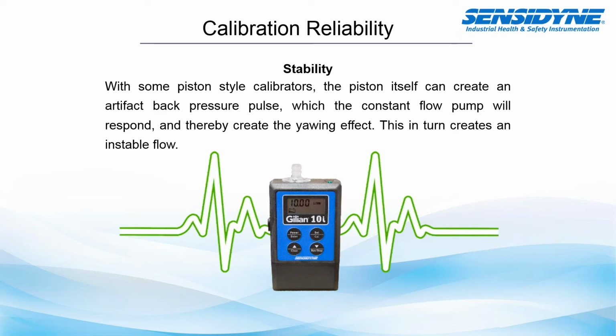Now, if your calibrator is trying to calibrate a pump that isn't steady, it's not going to actually see a steady value. And if you record that value, or you change the pump's calibration to an unstable value, it actually won't be displaying what that pump is actually bringing in.